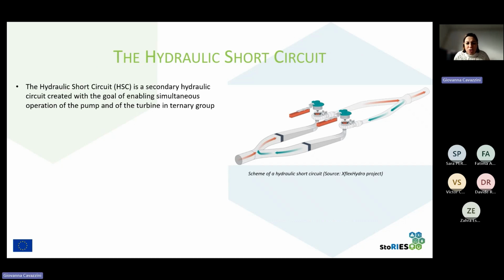Another important innovation introduced in pumped hydro power plants is the so-called hydraulic short circuit. It has been tested in real power plants in a recently ended European project, the XFlex Hydro project. It is a sort of secondary hydraulic circuit created with the goal of enabling the simultaneous operation of pump and turbine in the ternary group. As I said, in a ternary group you have two different hydraulic machines, one pump and one turbine. In the past, it was possible to operate them only individually, so only in pumping mode or only in turbine mode.